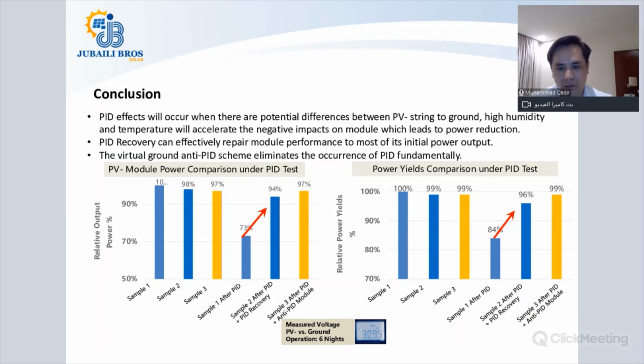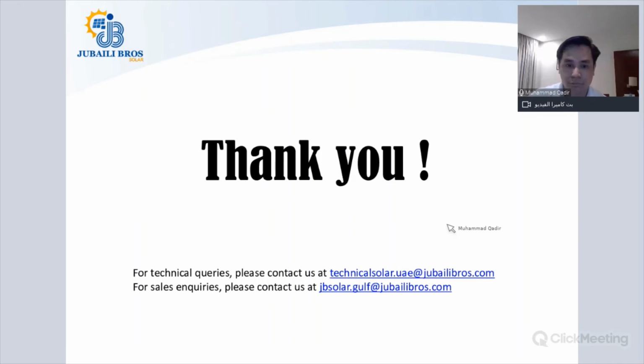So installations that happen are normally with a high voltage of 7 to 800 volts. So it is very good to have an inverter with a built-in PID recovery. With the new Huawei inverters, you will benefit a lot, and you will not be needing to use PID killer devices available in the market, or rather the built-in feature will cure the PID effect. You will just be needing to turn on the PID recovery function. You're using a built-in PID recovery feature of the inverter.